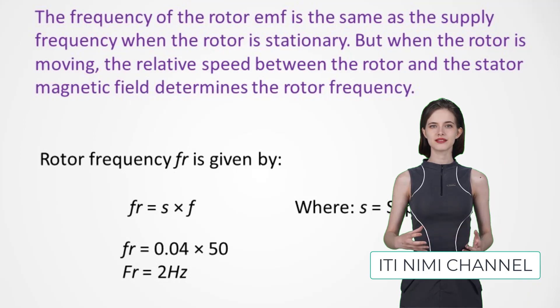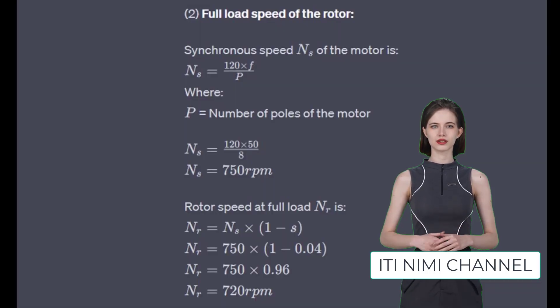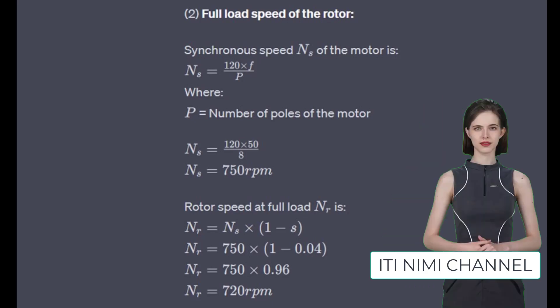Next, let's find the synchronous speed of the motor. The formula is: synchronous speed equals 120 multiplied by frequency divided by number of poles. This gives us a synchronous speed of 750 RPM.